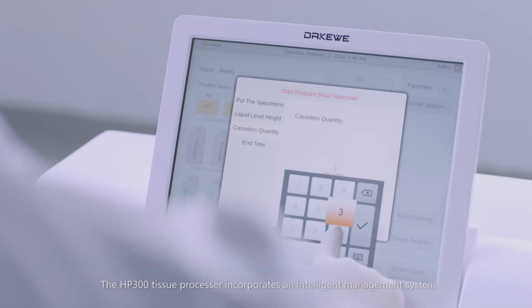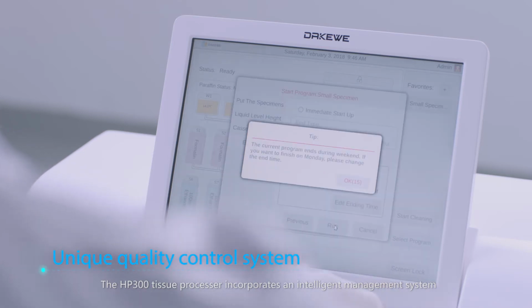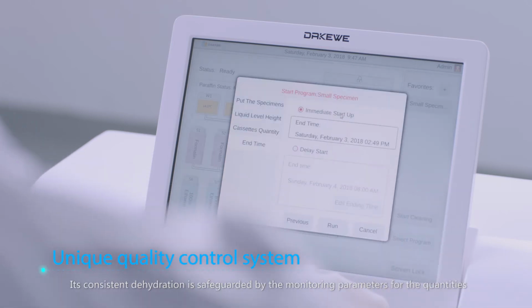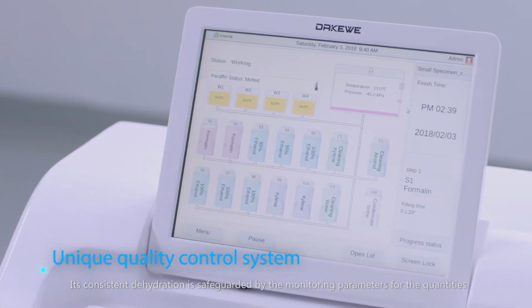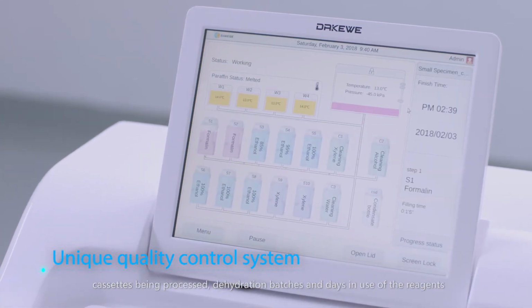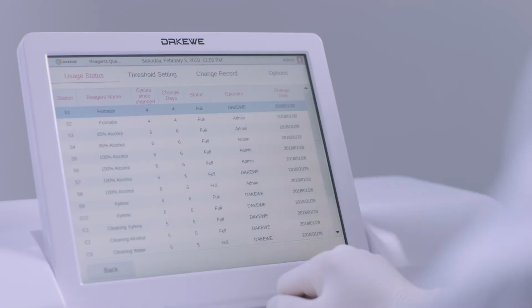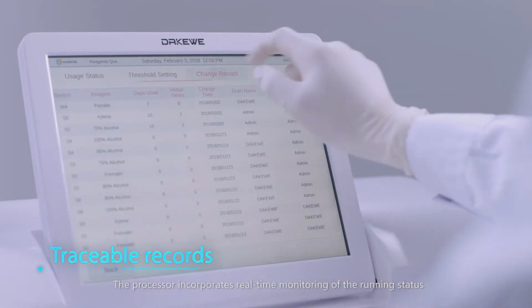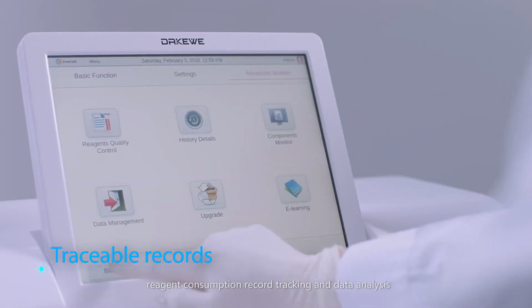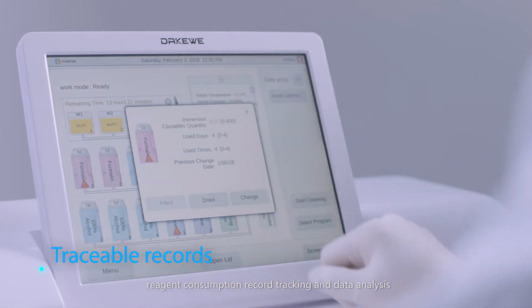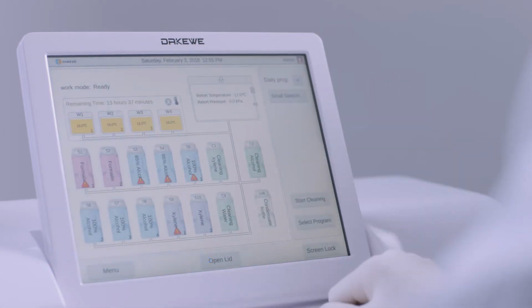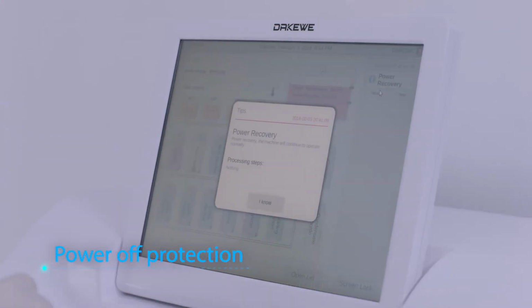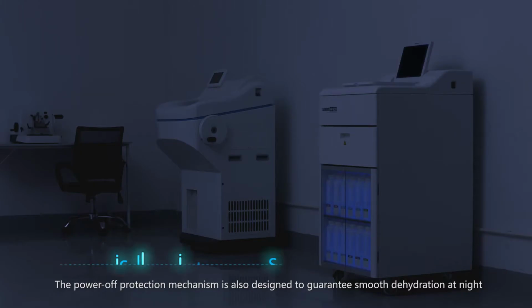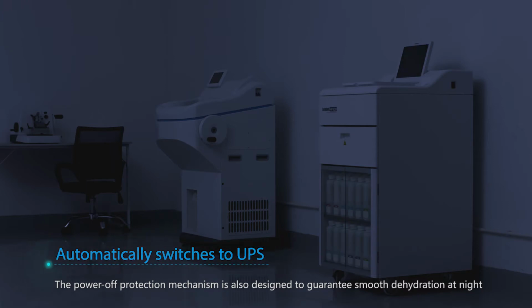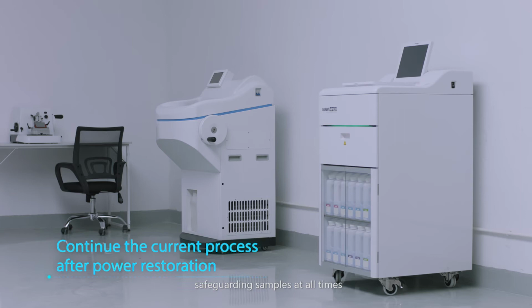The HP300 tissue processor incorporates an intelligent management system. Its consistent dehydration is safeguarded by the monitoring parameters for the qualities, cassettes being processed, dehydration batches, and days in use of the reagents. The processor incorporates real-time monitoring of the running status, reagent consumption record tracking, and data analysis. The power-off protection mechanism is also designed to guarantee smooth dehydration at night, safeguarding samples at all times.